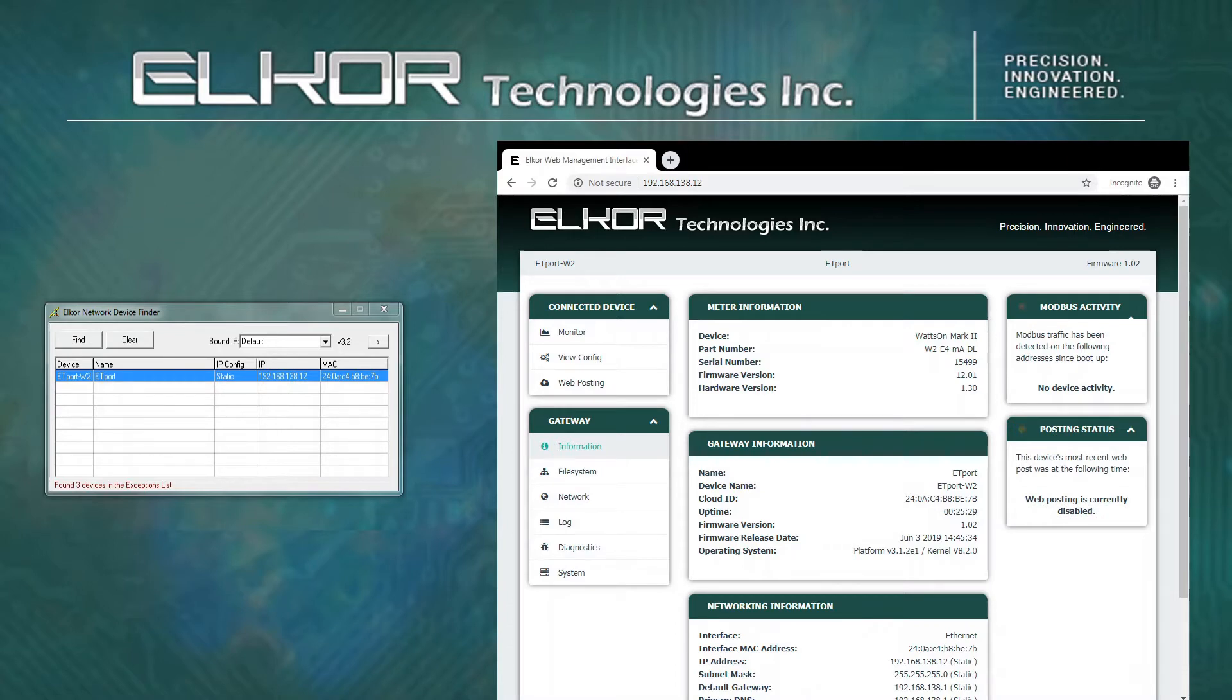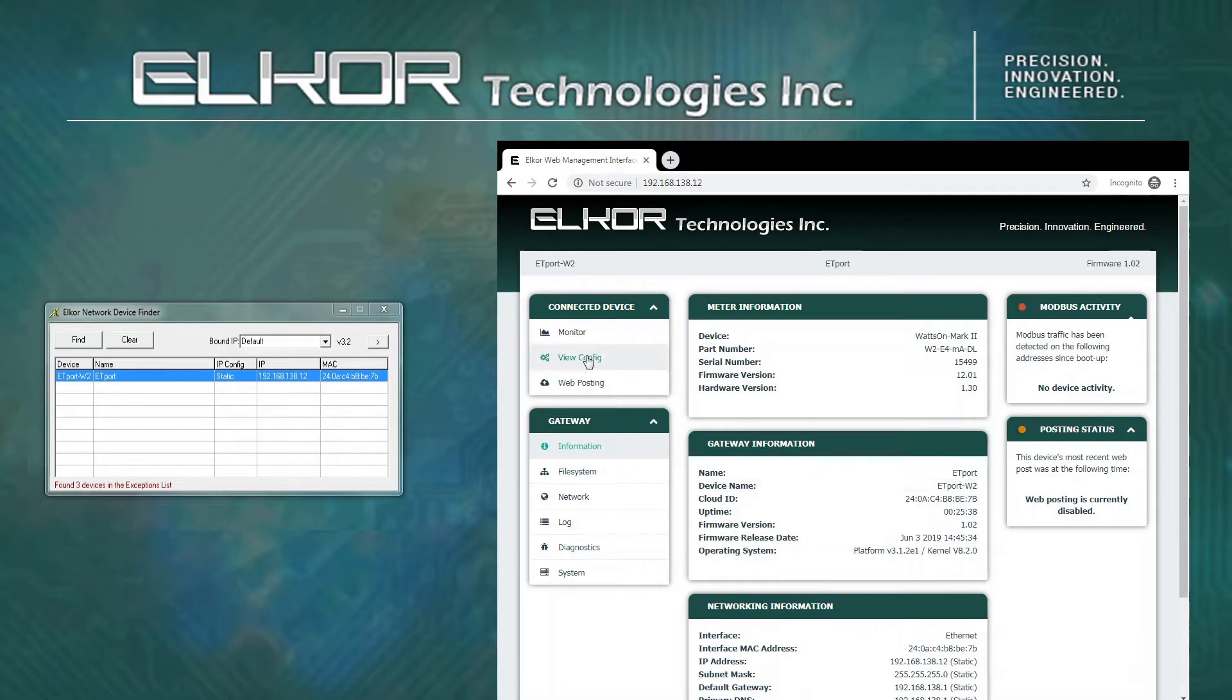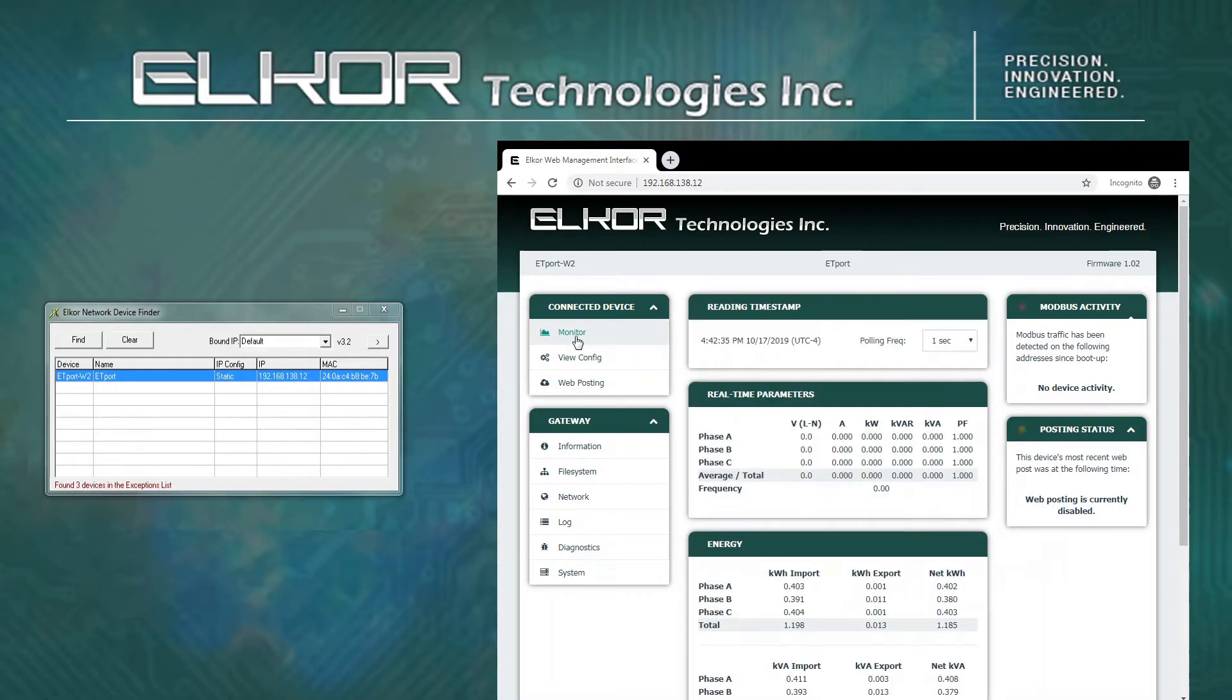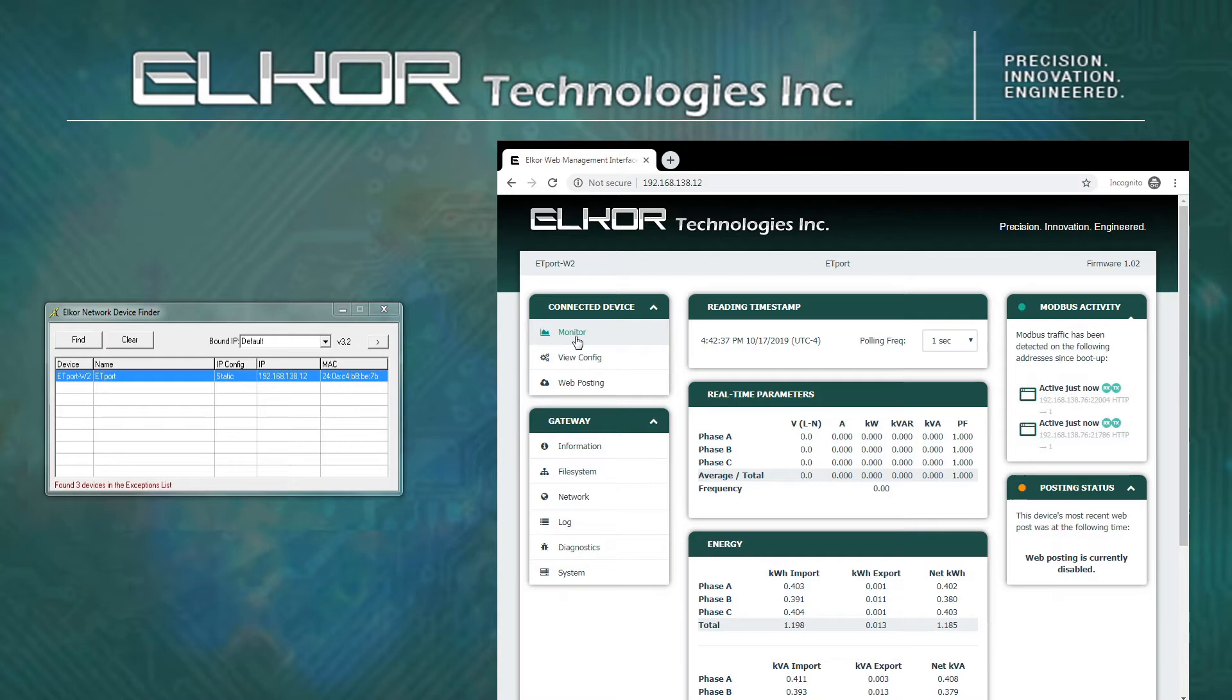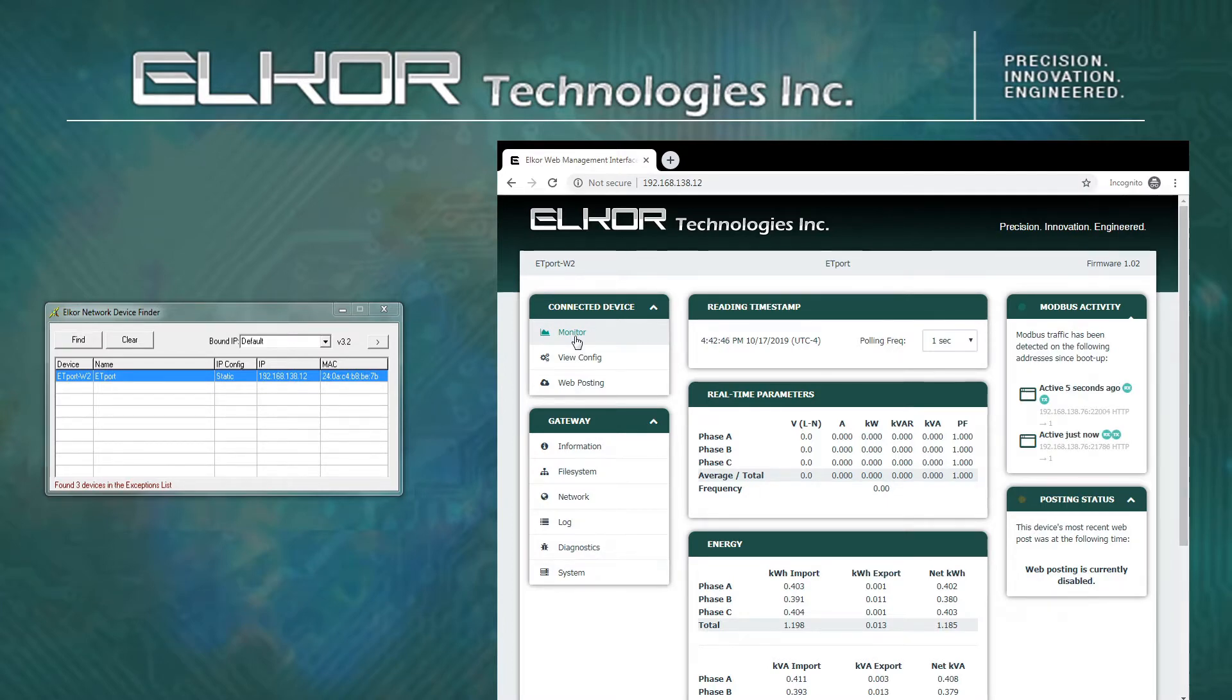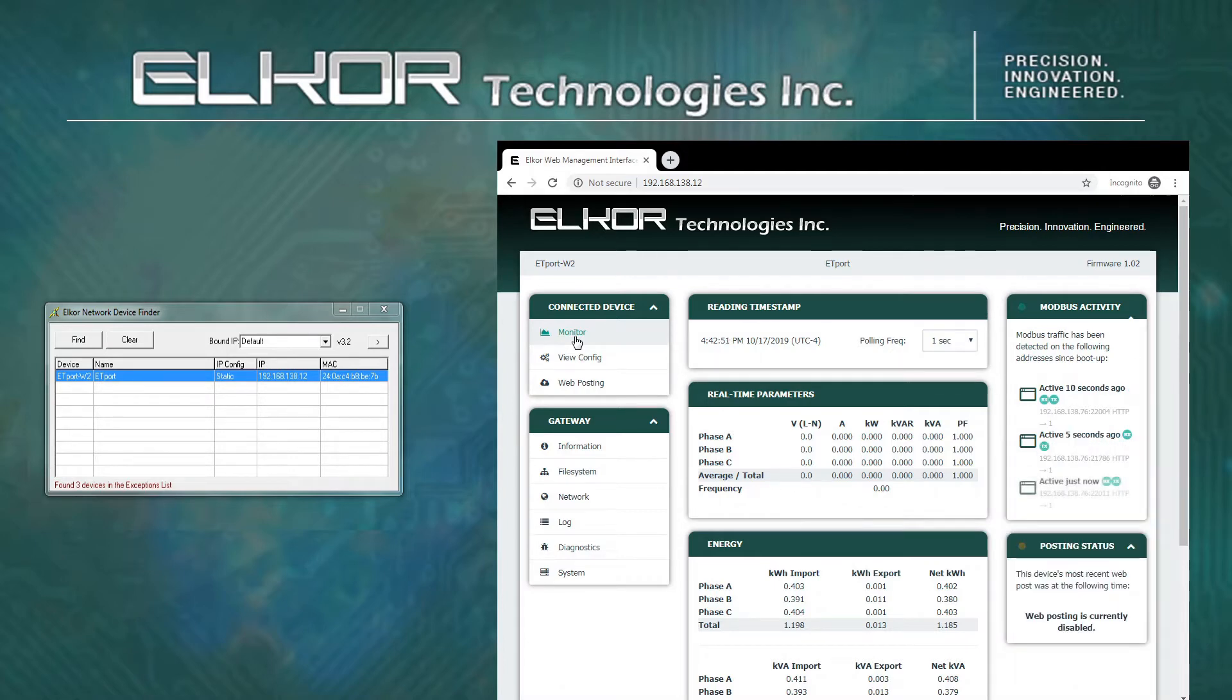The E4 Wattson Mark II and the ET port have many features, which we will cover at a later time. However, it is useful to demonstrate the Live Monitor page. Clicking on the Monitor menu item will show the real-time values as measured by the meter. These readings are updated once per second by default. In the case of the ET port, it will only work if it detects a Wattson Mark II meter connected to it with a Modbus address of 1. This is the default configuration for the Wattson Mark II.